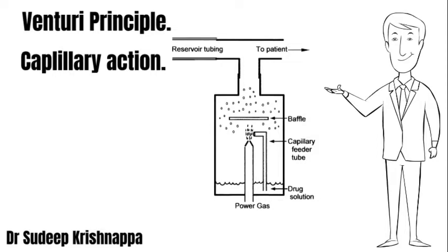The subatmospheric pressure which is generated continuously suctions or sucks up the fluid present in the chamber by capillary action. The moment the liquid reaches the orifice, the jet shatters this liquid against the baffling present internally, generating aerosols. This creates a mist which accumulates in the upper end of the chamber and subsequently moves on towards the patient.